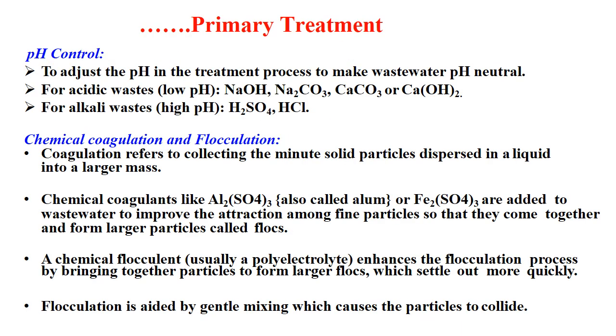Continuing about primary treatment: pH control is used to adjust the pH to make wastewater neutral. For acidic waste with low pH, we can use sodium hydroxide, sodium carbonate, calcium carbonate, or calcium hydroxide. When the water is alkaline with high pH, we can use sulfuric acid or hydrochloric acid.